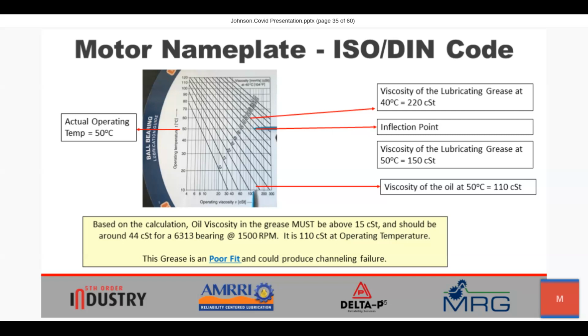Based upon the size and speed with which the shaft is turning, this bearing wants no less than 15 centistoke, but preferably 44 centistoke viscosity from the grease. If we're using a general purpose grease, like we see here, we would have 110 centistoke, which is way too thick to satisfy appropriate lubrication requirements for the bearing in the motor.